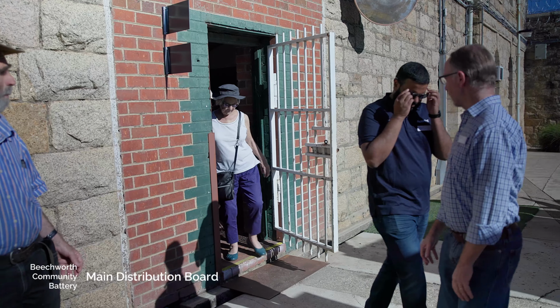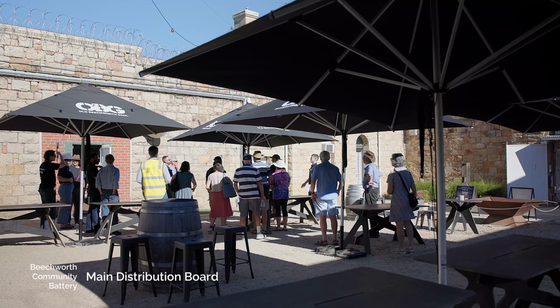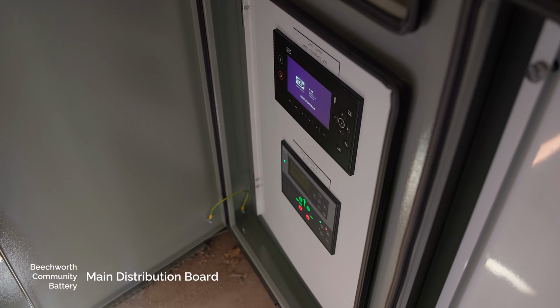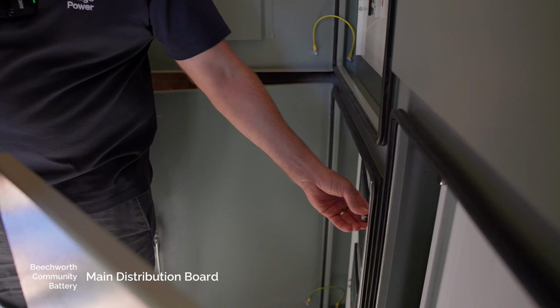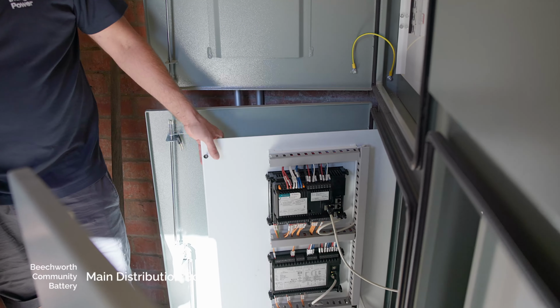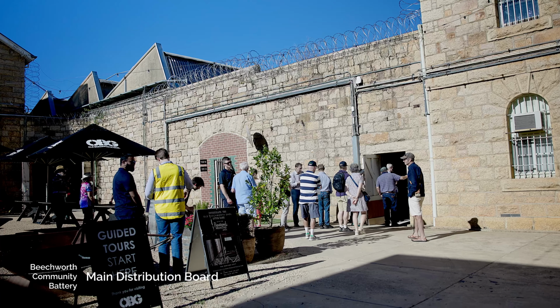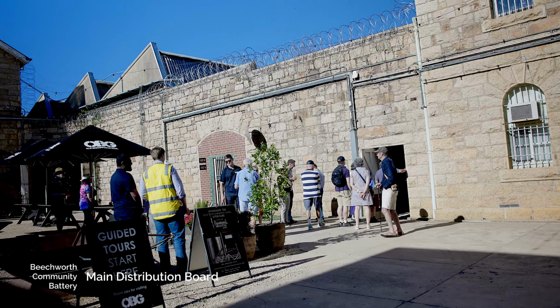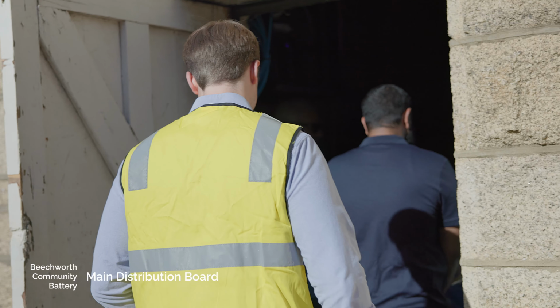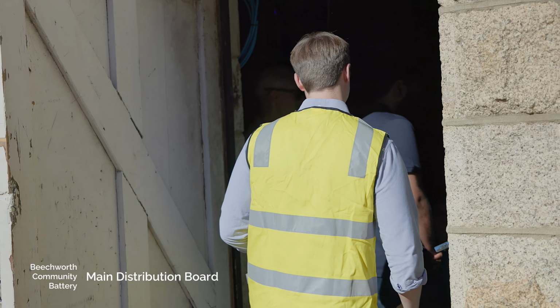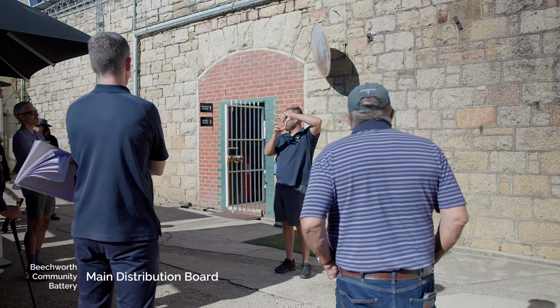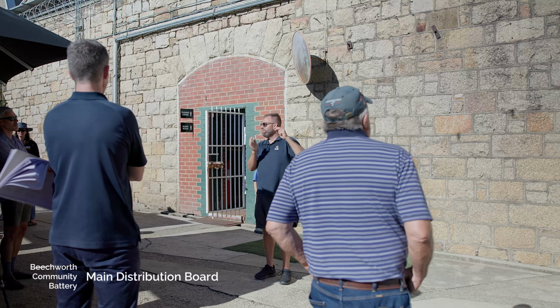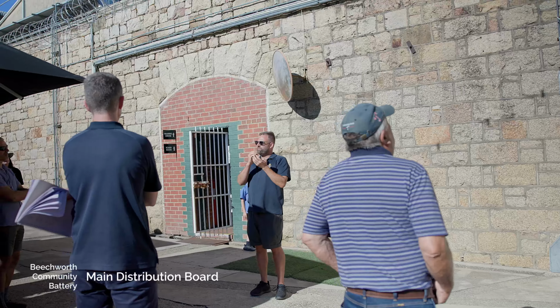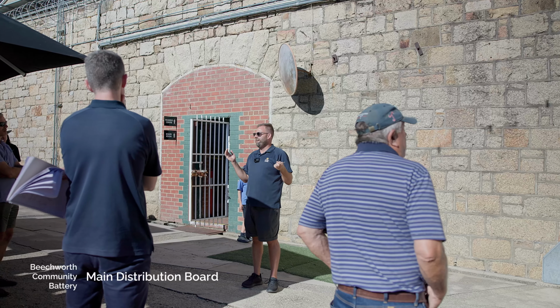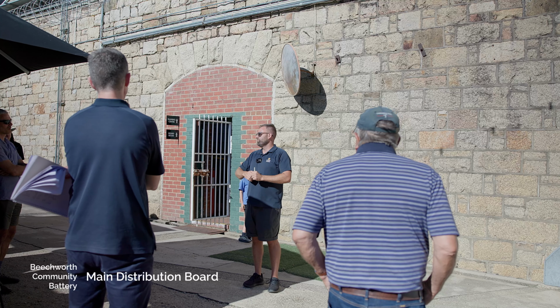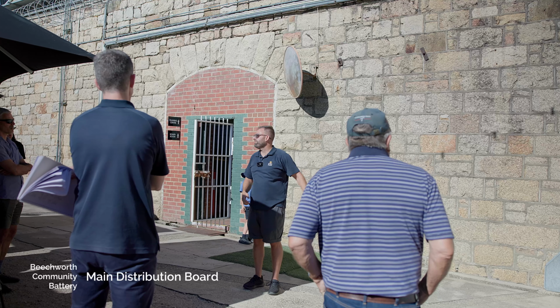This is the main distribution board. This board was incredibly old, actually older than the switchboard out there, just due to its age and the facility. It had completely rusted through, there were holes in it. All the old bus bar was cracking, which is incredibly dangerous. Eventually that bus bar insulation will flake off, and then it just takes one bug or something and it will just go - it'd blow that whole door off, to be honest.